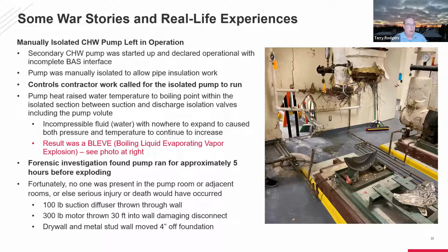Another war story. This is a real life example where a secondary chill water pump was started and declared operational, but the BMS or BAS, building automation system, work was not complete on it. The pump was manually isolated to allow pipe insulation work. The controls contractor later doing work ended up sending a command to start the pump that was isolated. The pump heat raised the water temperature to the boiling point because it had nowhere to go. It's not moving any flow.